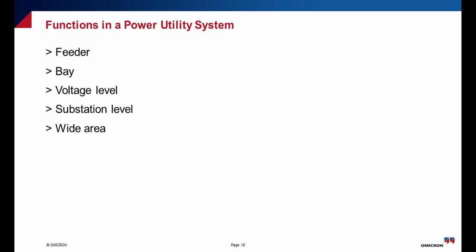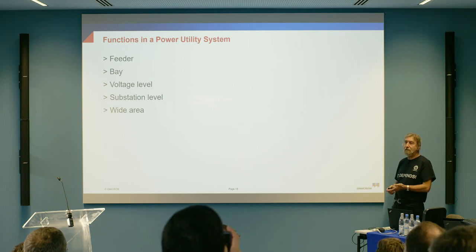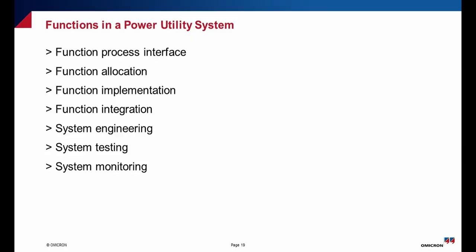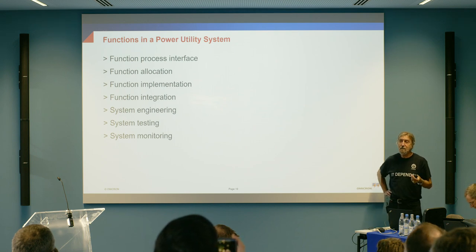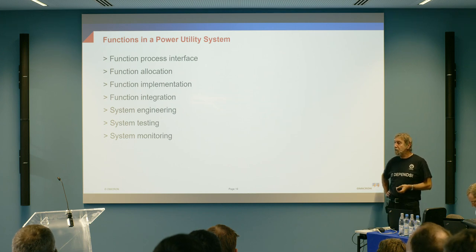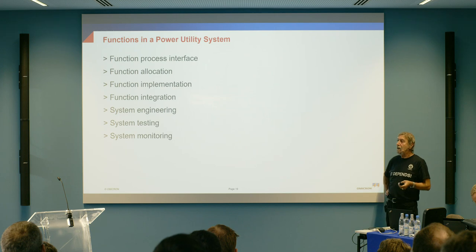Many of these functions can be implemented at different levels in the power utility system — at the feeder level, the bay level, the voltage level, the substation level, or at the wide area. When we talk about what kind of functions we need, first of all we have to have a process interface, because any protection, automation and control function needs information about certain parameters of the electric power system and needs to know the status of the switchgear in order to determine the real-time topology of the grid and adapt its behavior for changing system conditions.